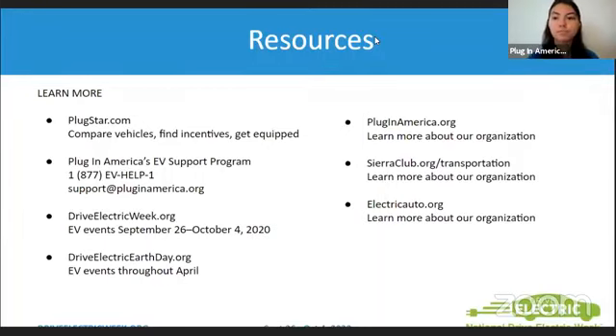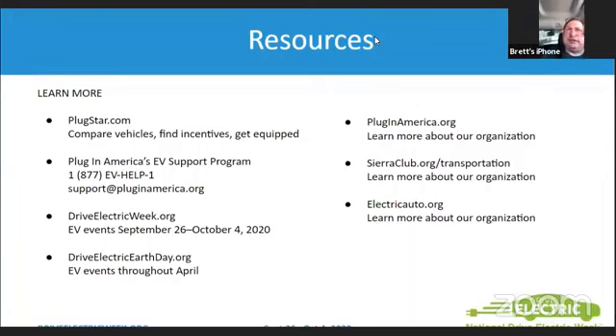That's a great question. I can take that one. Once you get to that 80% capacity, it's not a sub panel upgrade. It's actually a main panel upgrade. So from the main panel, yes, you want to make sure that you have at least 125% protection on your EV circuit. So if you don't have that protection at your main panel, you need to upgrade to a larger panel.